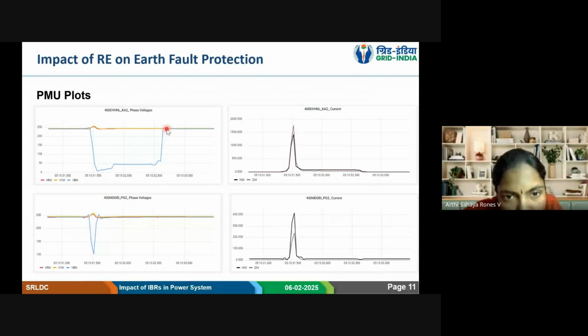So it is coming back. The voltage is coming back. This fault was a transient fault. That's why at the time of reclose, we are not seeing any dip. If you see the reflection of this Devanahalli line fault in a nearby station, let us say Tumkur, these are the stations in Karnataka, it is something like that.